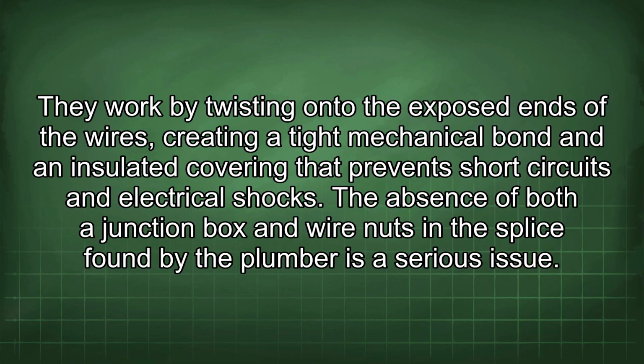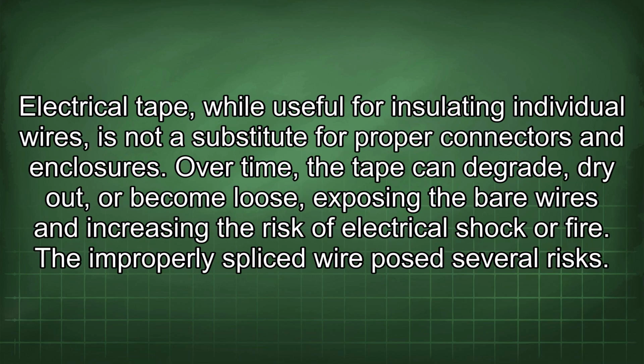The absence of both the junction box and wire nuts in the splice found by the plumber is a serious issue. Electrical tape, while useful for insulating individual wires, is not a substitute for proper connectors and enclosures. Over time, the tape can degrade, dry out, or become loose, exposing the bare wires and increasing the risk of electrical shock or fire. The improperly spliced wire posed several risks.